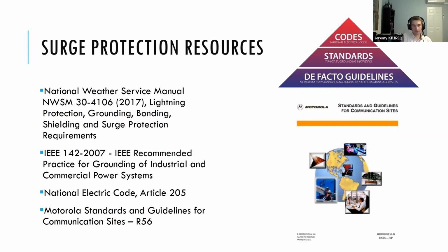And this last resource is the one, obviously, that I'm most familiar with, but it builds on really all of these, and it's Motorola's R56 manual, which contains a whole breadth of topics regarding building out a communication site, but it has an entire section on grounding and surge protection. And the same thing, it builds on NEC, on IEEE, it builds on all these codes and standards in order to have, as that pyramid states, a de facto guideline, right? So a above and beyond best practice specific to communications, wireless communications sites.